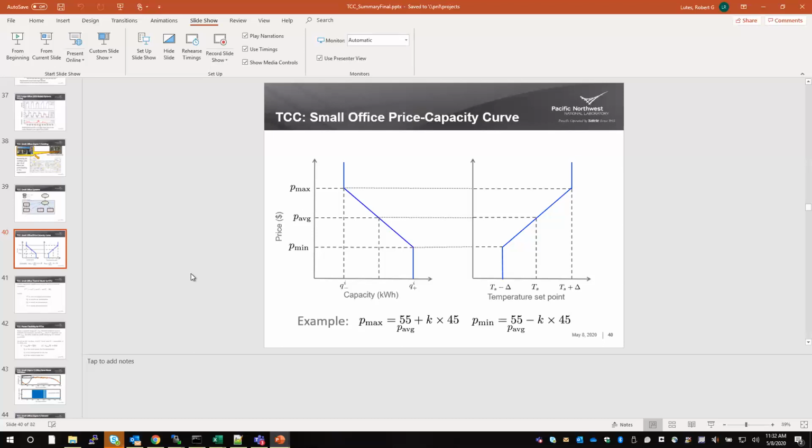And then your third question about overrides. We do a couple of different ways we override. One is a global override where the building operator can basically override the entire building from responding to any of the actuation signals that Voltron sends. And we only support BACnet.